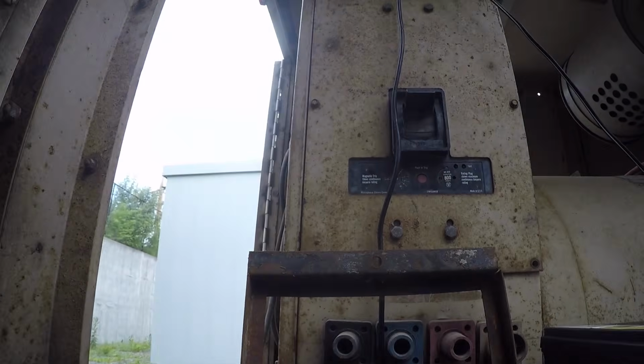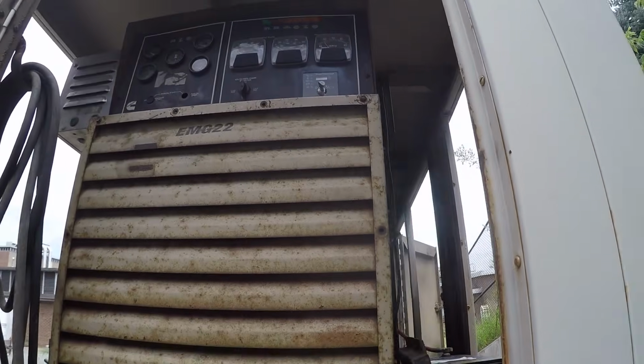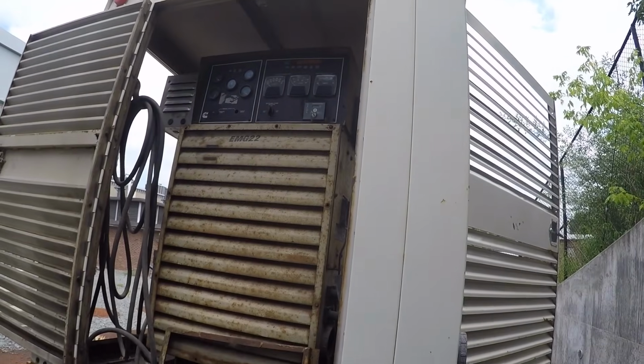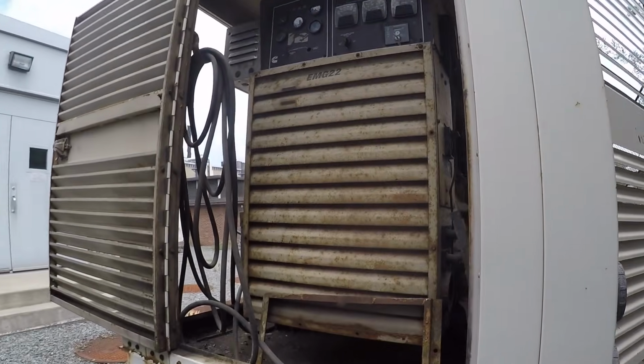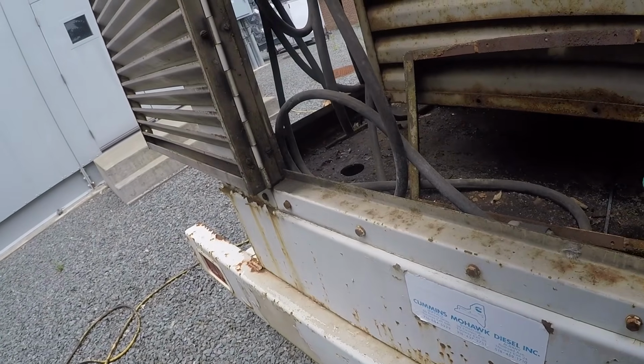This old Cummins is a trooper. She doesn't like the winter when it's cold, but today fired second crank cycle. So the breaker did reset. We were able to check the voltage across the phases, had about 470 volts between all the phases. So it looks like we're getting voltage.